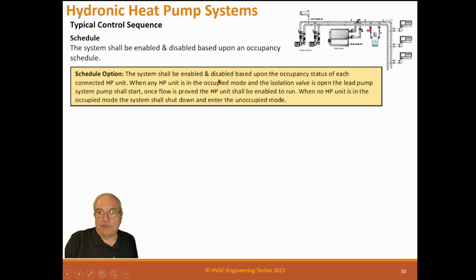When any heat pump is in the occupied mode and the isolation valve is open to the heat pump, the lead pump shall start. Once flow is proven, the heat pump unit shall be enabled to run. When no heat pump is on and the unit is off, it shall shut down and enter the unoccupied mode.